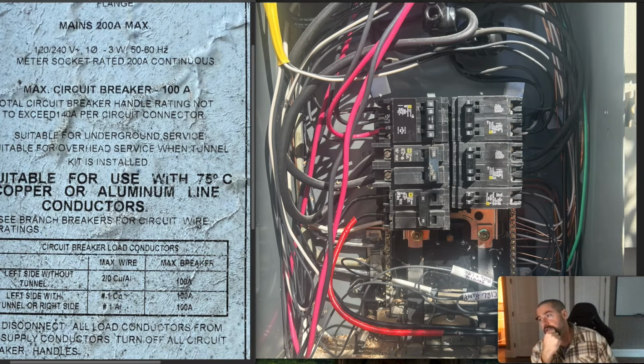you can't actually back up the entire home downstream of a 100 amp breaker. So, you know, if you had a meter collar, such as the Tesla backup switch or the Enphase meter collar. Franklin's about to come out with a meter collar, and I believe EG4 is as well. That can kind of eliminate these issues where you just have a meter collar installed right behind the utility meter, and it severs that connection upstream of this bus bar during an outage. But if you're not using that and you're using a traditional transfer switch or microgrid interconnect device, you'd kind of be stuck with partial home backup in this scenario.